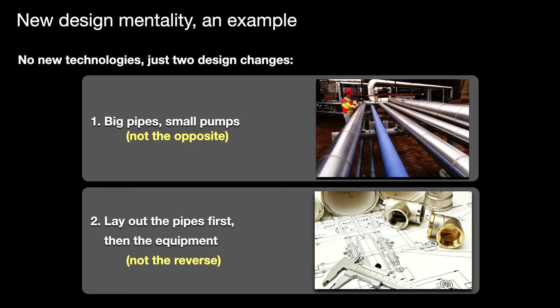Now, the pipe fitters actually like this because you pay them by the hour. They mark up the extra pipes and fittings, and they're not paying for your bigger pumping system or your bigger electric bill forever. But for you as owner, it's smarter to make pipes fat, short, and straight than skinny, long, and crooked. Thus, low-friction pipes make the blue pump so tiny it looks like a decimal point error.